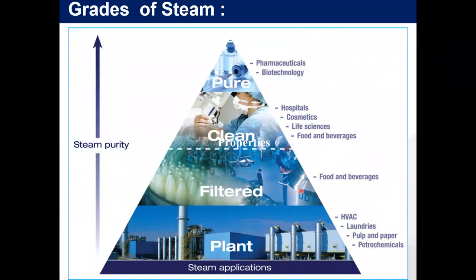So we use our stainless steel filters with, say, a 5 to 25 micron filter to take out any particles that may have formed in the steam. Particles are mostly from erosion, so rust in the pipes, carryover from the boiler. We try and catch all of those and filter them out. With the filters, especially for food and beverage, to reduce cost, you would have these as close to process as possible. So pipe work after a filter should be stainless steel because it aids in the purity of that steam, or if not, being able to rust and so on.